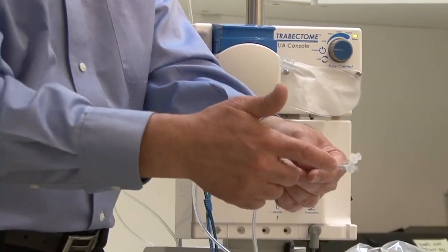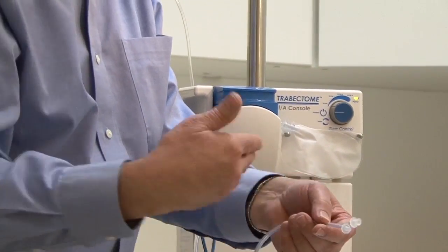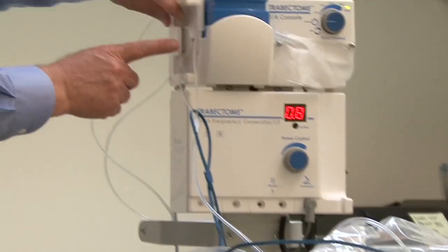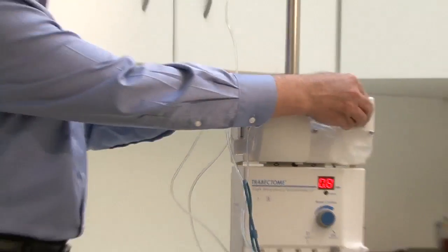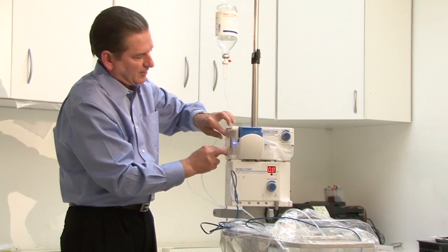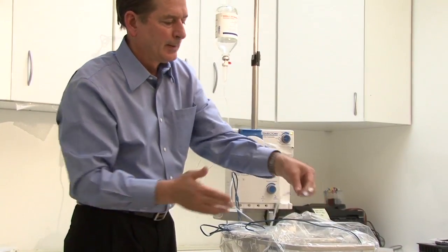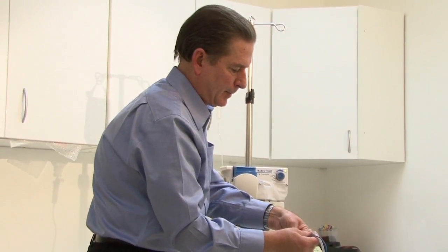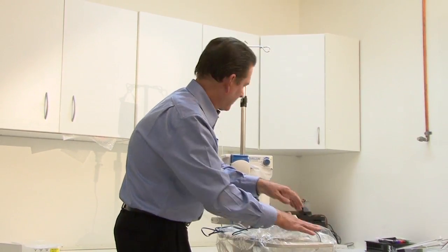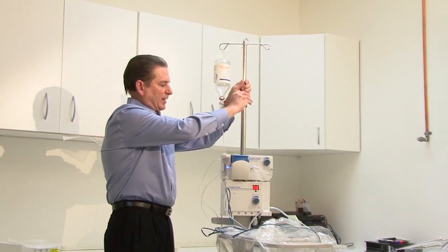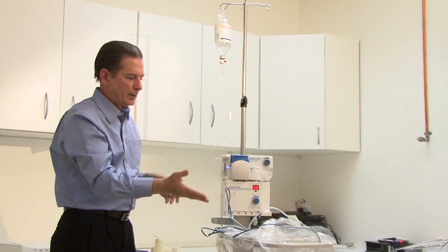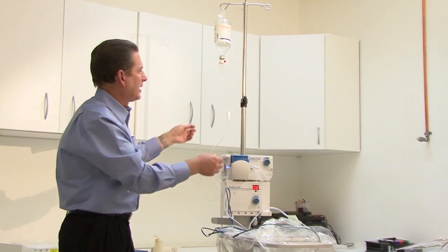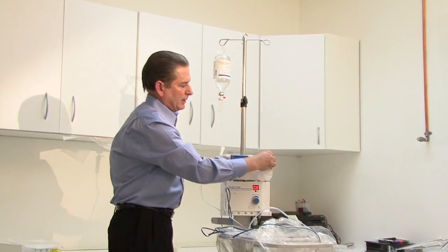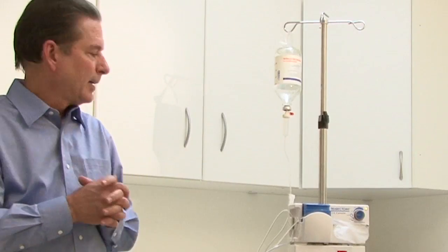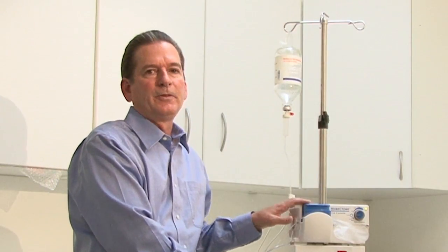However, if we go to connect the handpiece, we turn this off and it just keeps flowing, don't let that be an issue. All it means is that this hasn't really been inserted properly. So just go ahead and turn on the light, readjust this, try again, and that should solve the problem. This should turn off. We go ahead and connect our handpiece and finish the prime. So that's the most common issue with setting up, where sometimes the tube isn't inserted and we'll see that the irrigation doesn't fully shut off. Other than that, it's really quite straightforward and easy to set up and prepare for surgery. And I think you'll find that after you've used the equipment just a couple times, you feel very comfortable with how simple it is to set up and have ready for surgery.